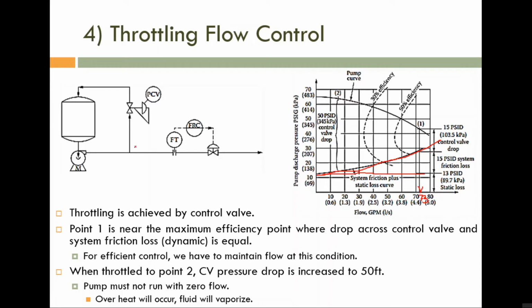Now here a control valve is also included, which means a control mechanism is included. Here we have two dynamic resistances. The dynamic resistance offered by this one is actually fixed. This is a dynamic friction, but it is constant if the flow rate is constant. But this one is a variable resistance: if you open the valve, the resistance will definitely decrease. So the resistance offered by the orifice restriction is included here, in addition to the friction loss.